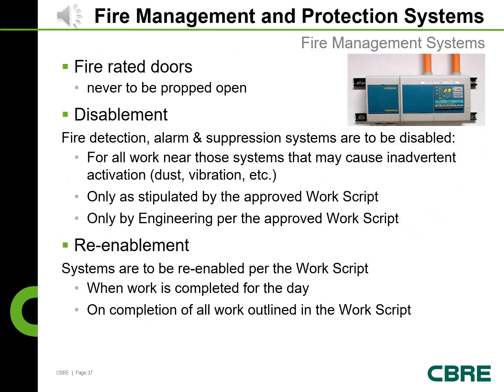Fire management and protection systems. Fire-rated doors are never to be propped open. Disablement. Fire detection, alarm, and suppression systems are to be disabled for all work near those systems that may cause inadvertent activation, such as dust, vibration, etc., only as stipulated by the approved work script. Only by engineering per the approved work script. Re-enablement. Systems are to be re-enabled per the work script when the work is completed for the day, on completion of all work outlined in the work script.